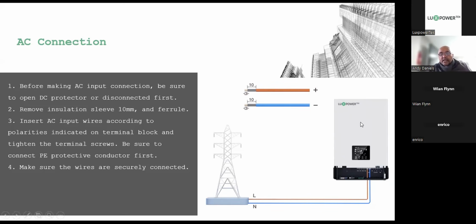Otherwise, you're going to get [overheating] of the cabling, and obviously you're going to compromise the circuit breaker and the connection point. So please make sure that you use the right size cable. We obviously recommend that you remove the insulation, I mean, it's common sense, and ferrule them.